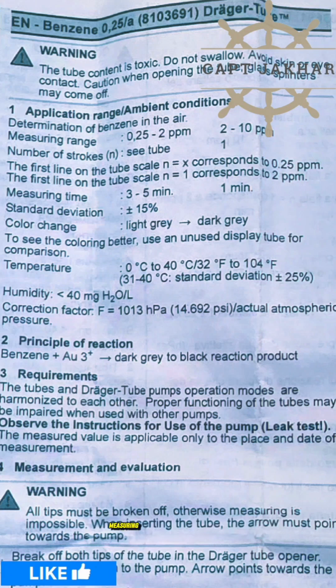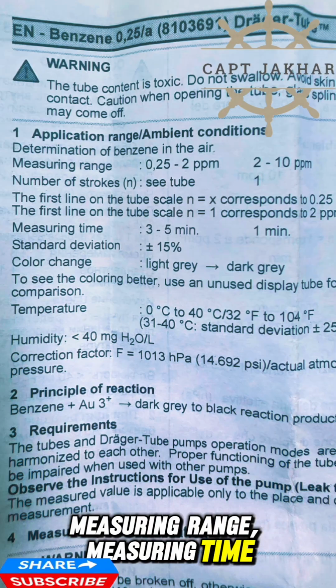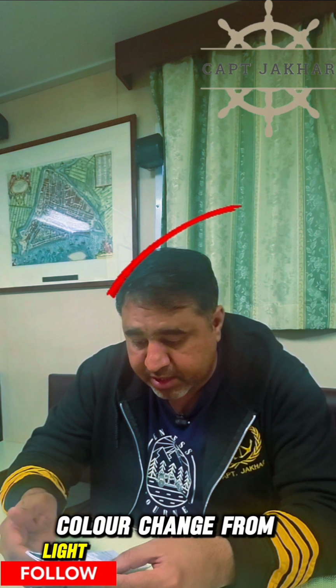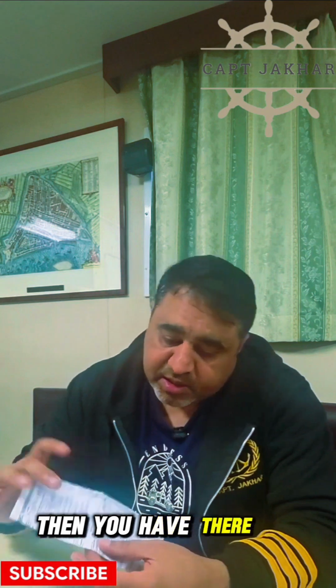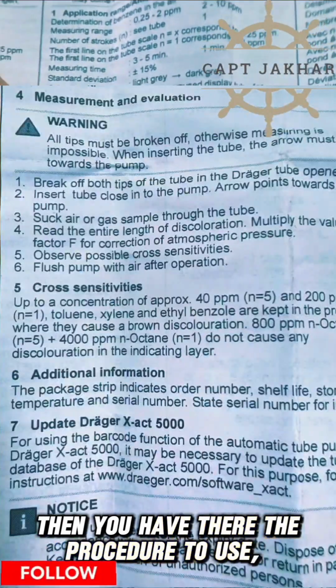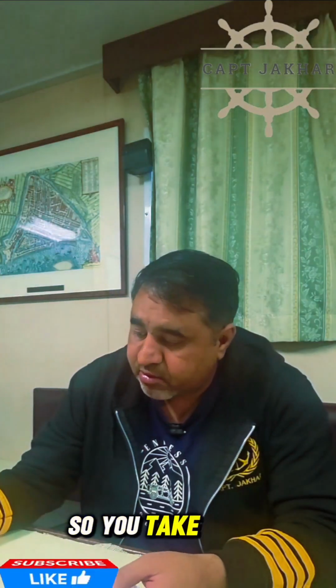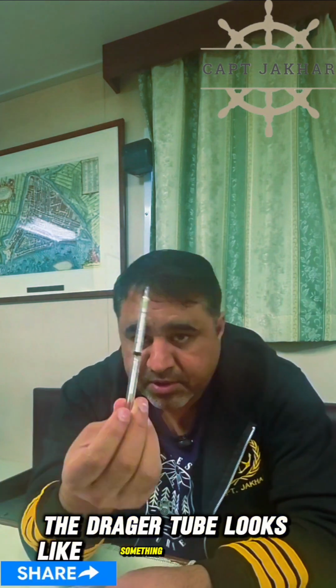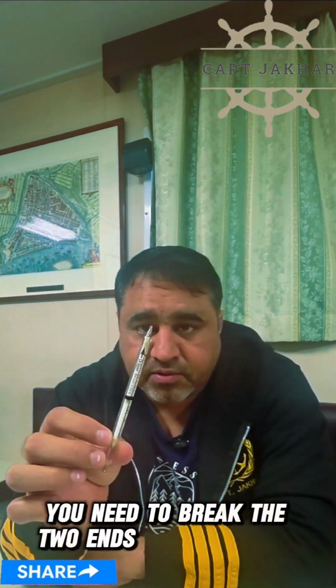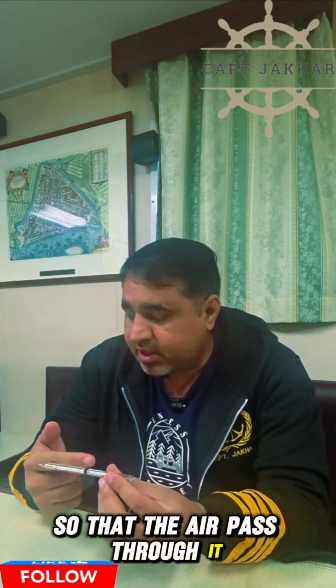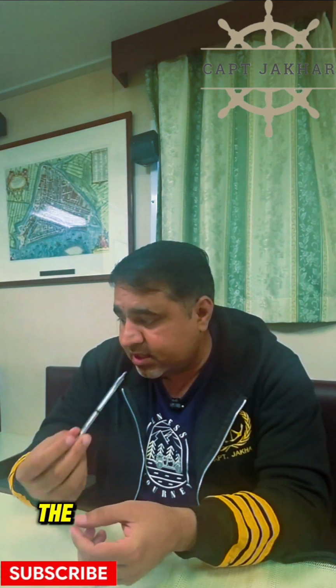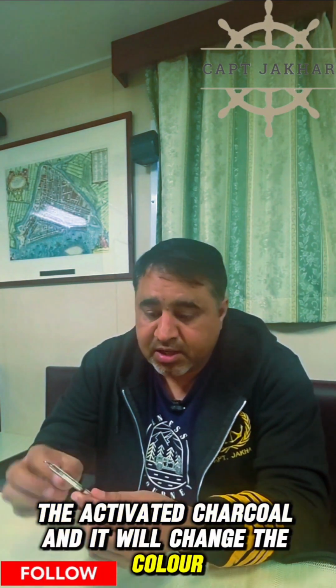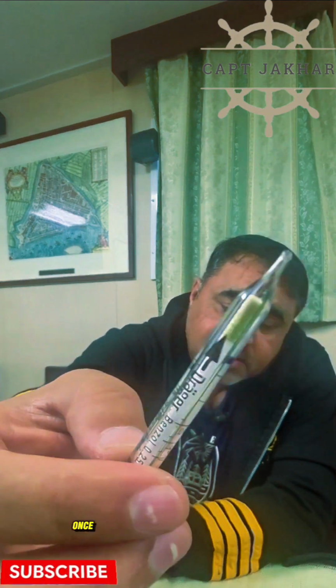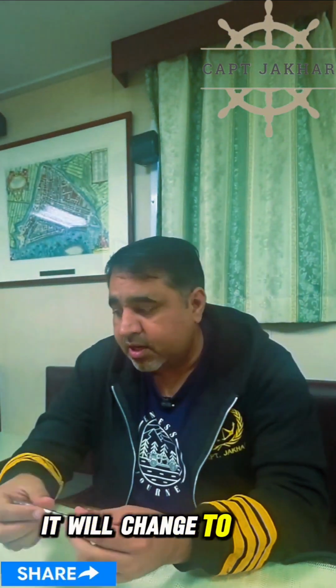You can see on your screen: measuring range, measuring time 3 to 5 minutes, color change from light gray to dark gray. Then you have here the procedure to use, steps 1 to 7. So you take out a Dräger-Tube. The Dräger-Tube looks like this. To use it, you need to break the two ends so that the air passes through it and reacts with the chemical inside, the activated charcoal, and it will change the color. Like this tube, it's light gray. Once you have some concentration, it will change to dark gray.